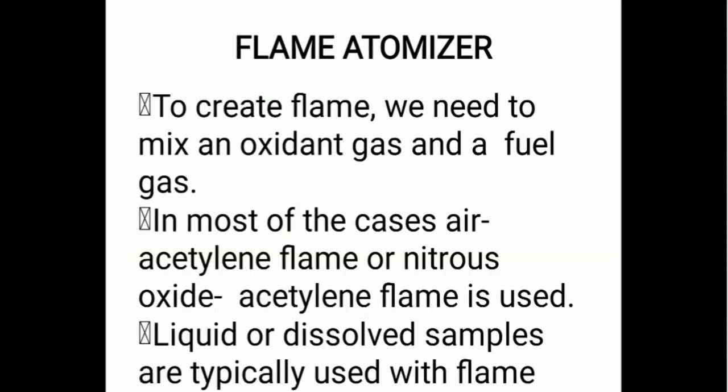First, let's talk about the flame atomizer. To create a flame, we need to mix an oxidant gas and a fuel gas. In most cases, an air acetylene flame or nitrous oxide acetylene flame is used. Liquid or dissolved samples are typically used with a flame atomizer.